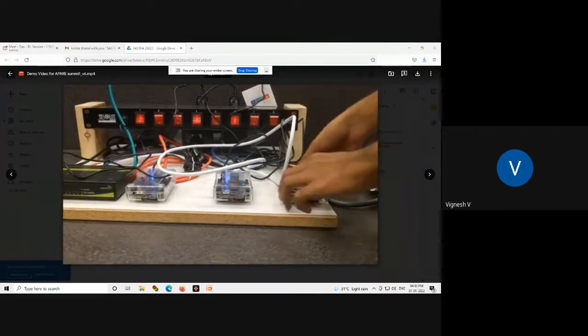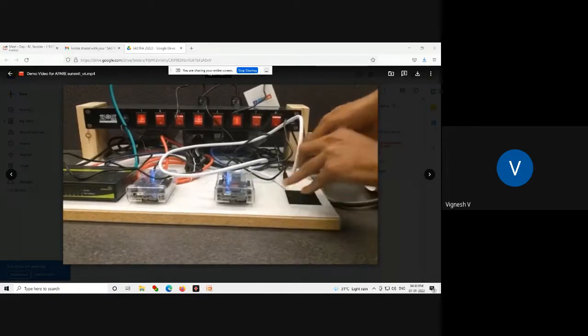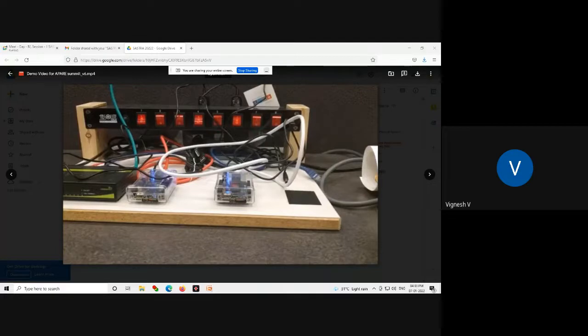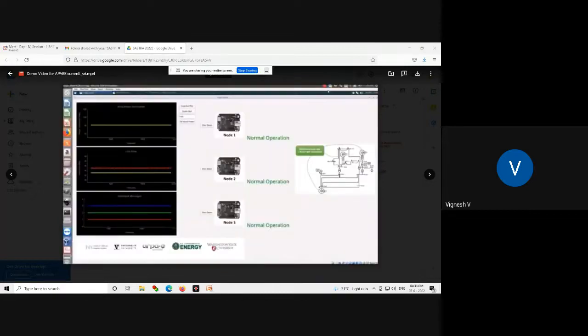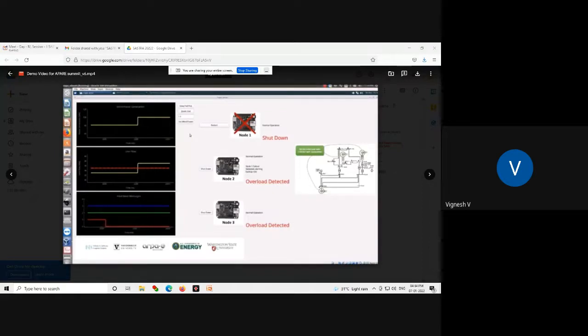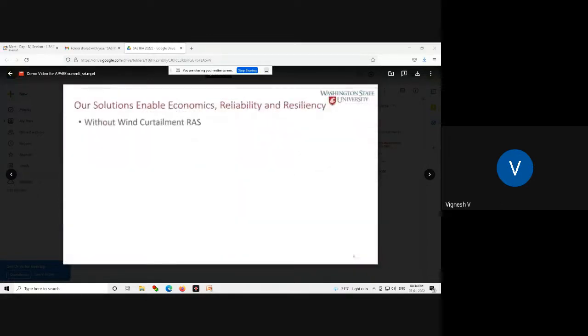I'm going to switch off the power supply to one of the nodes and remove its communication link. The system detects this failure. Node 1 was shut down, and the other two nodes detect its failure. They start performing the function of the malfunctioning node, take up that burden, and detect the overload caused by the increase in wind. They curtail the wind, and the system comes back to normal operation, with the line overload detected and everything restored to normal operating conditions.